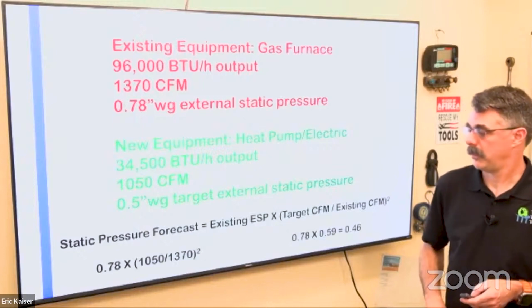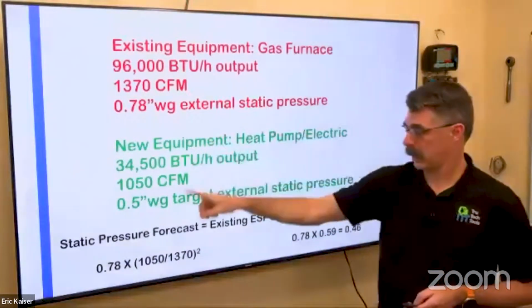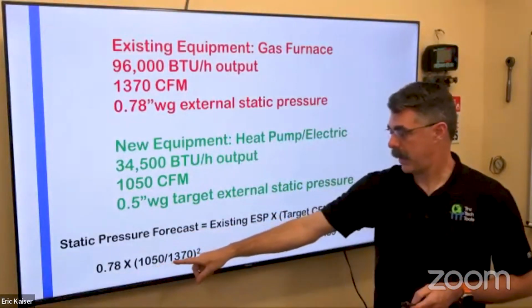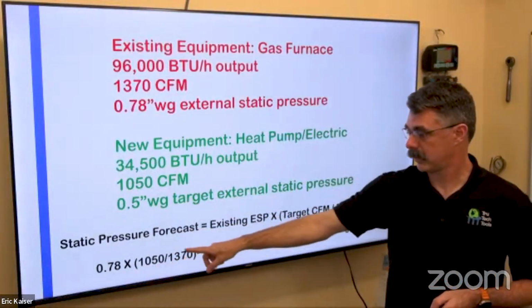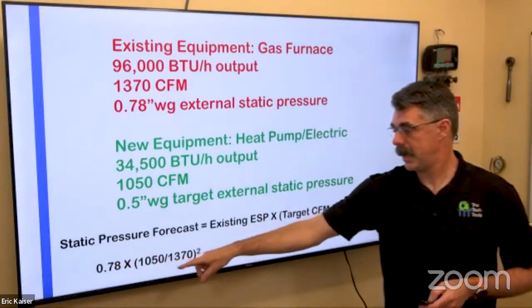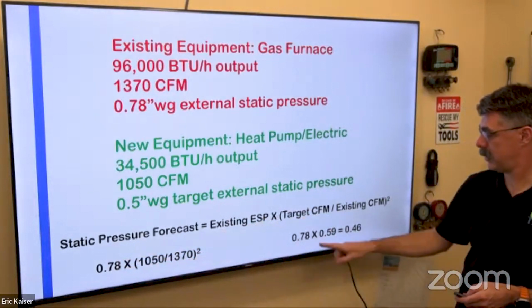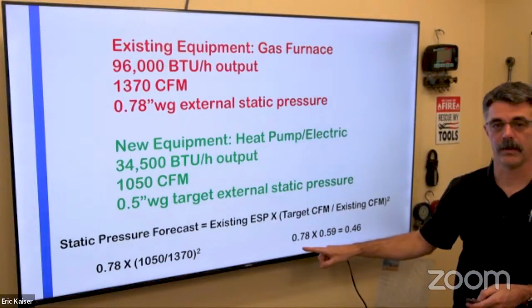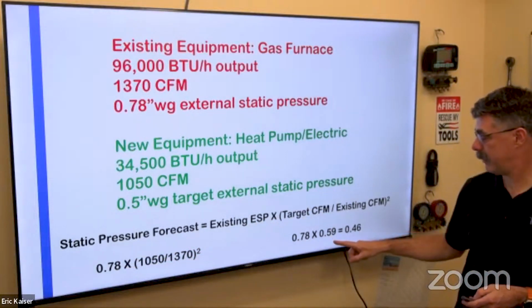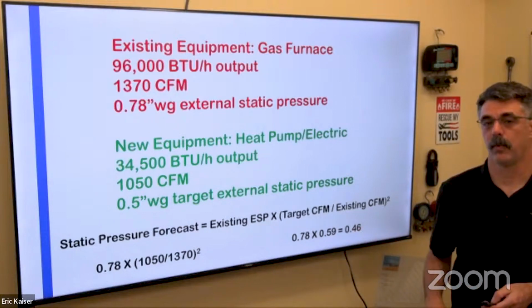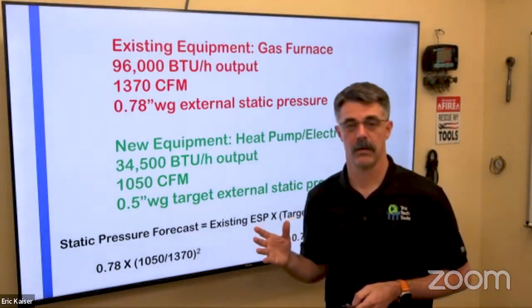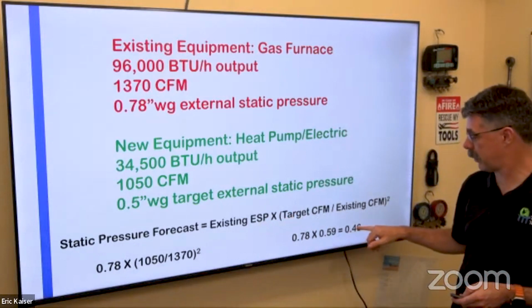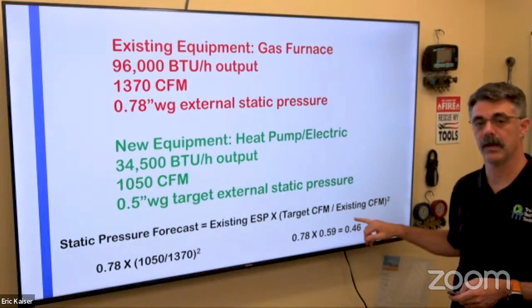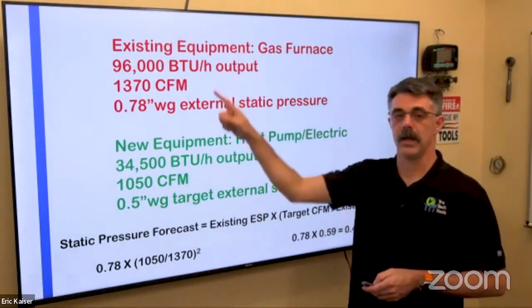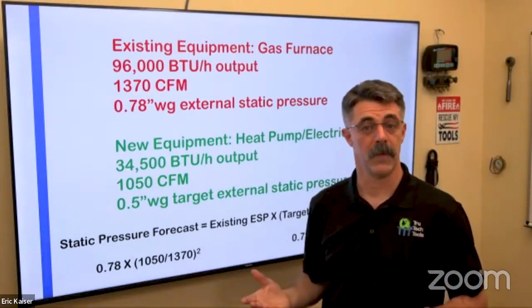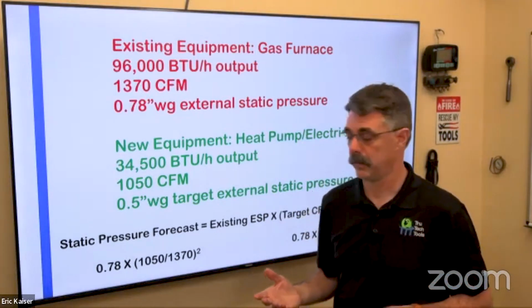So in the end, it would look like this, right? 1,050 divided by 1370 squared, 0.78 times that number, which is going to equal out to 0.78 times 0.59. We're going to end up with roughly 0.46, if you see that over here, 0.46 inches of static pressure if we did this. Now, that's pretty doggone good.